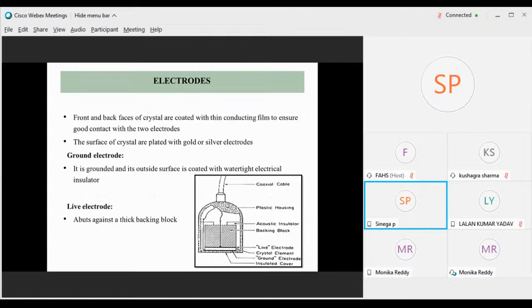So electrodes. The crystal is placed between the electrodes, which are thin conducting layers, front and back. The surfaces of the crystal are plated with gold or silver electrodes, and the crystal is grounded. It is grounded in order to avoid electrical shock. The live electrode is placed against a thick backing block, whereas the ground electrode faces towards the patient, with a watertight electrical insulator in order to avoid electrical shock.